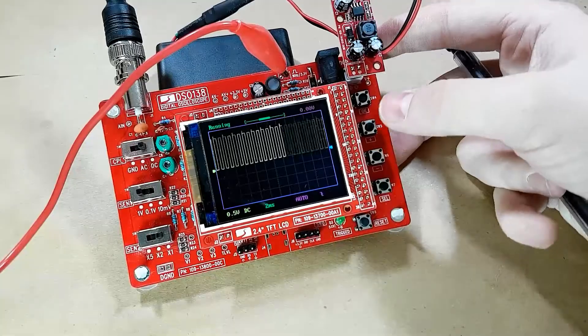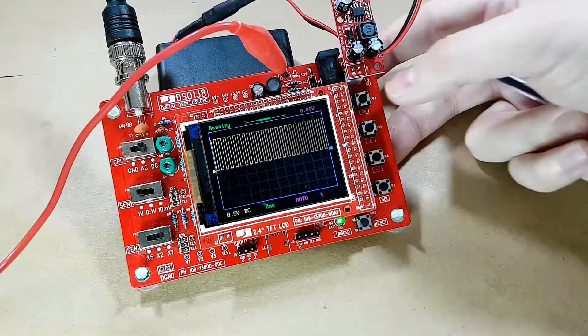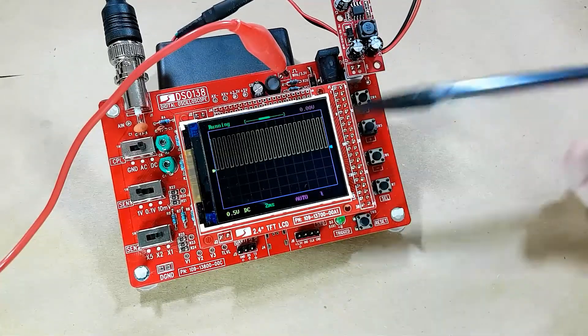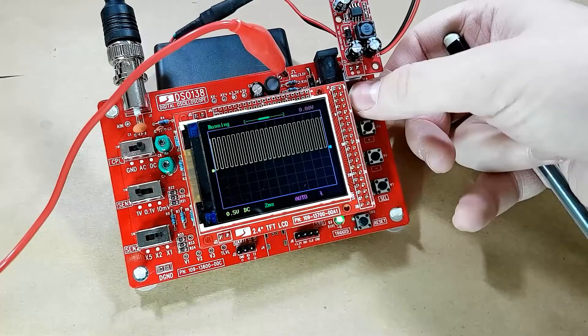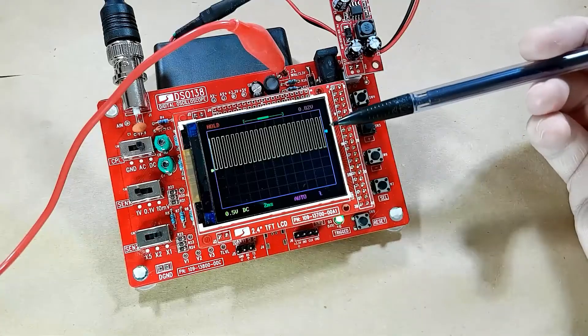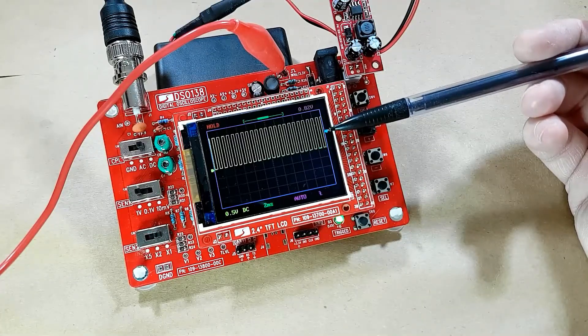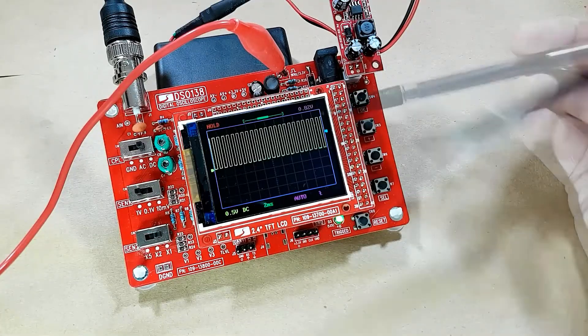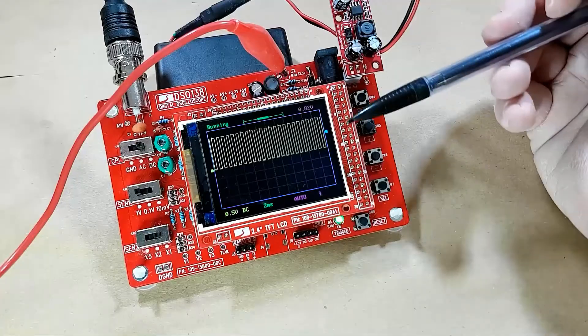One feature this does have is if you select the trigger selector and hold the OK button for two seconds, it will actually place the trigger in the middle of the waveform. So that's the auto-center for the trigger level.